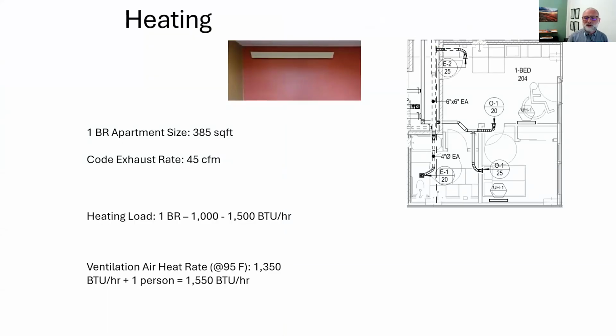While the building has small SEDU units and about 20 one-bedroom apartments, we'll look at the one-bedroom units as the worst case. The largest one-bedroom units are 385 square feet. Running loads on the building, we find the one bedrooms to range from approximately 1,000 to 1,500 BTUs per hour in heating load. The heating loads assume there's no activity in the apartments. We're not taking any credit from occupants, heat, light, or other equipment. This is to make sure that we're looking at a worst case scenario.